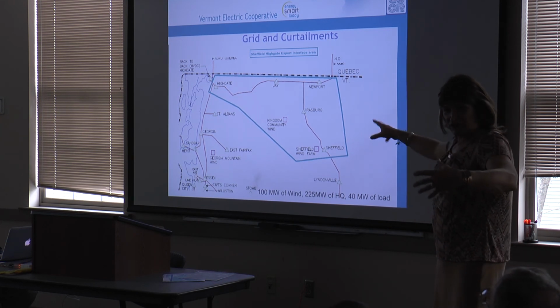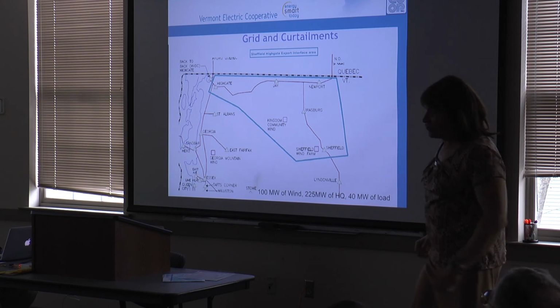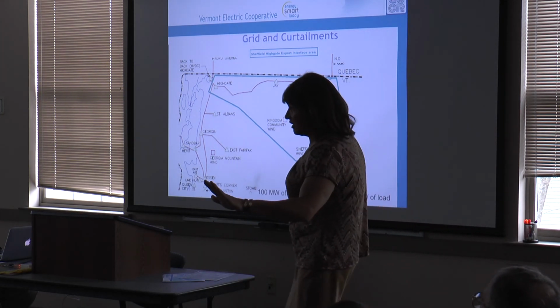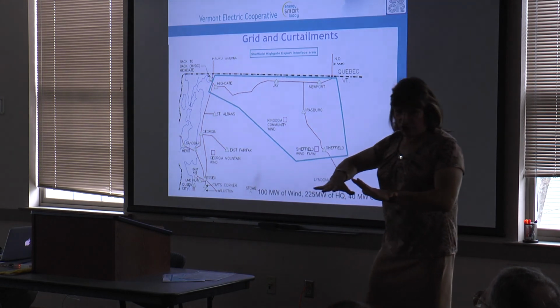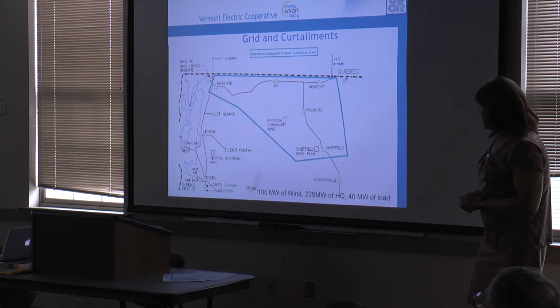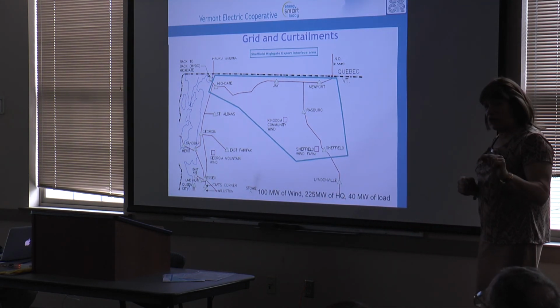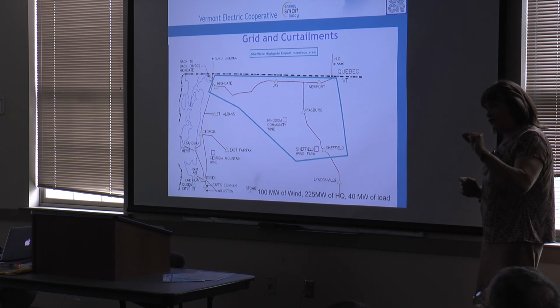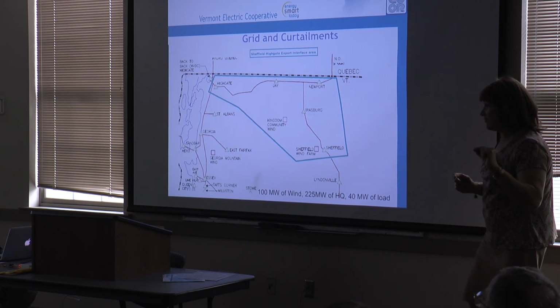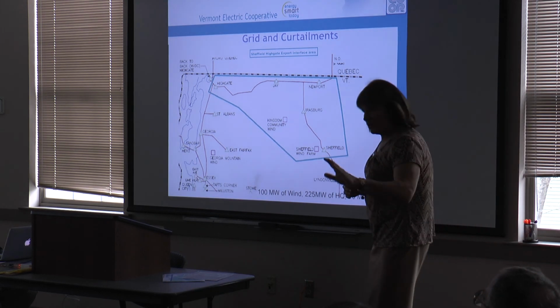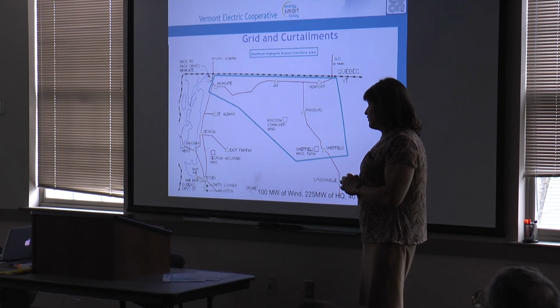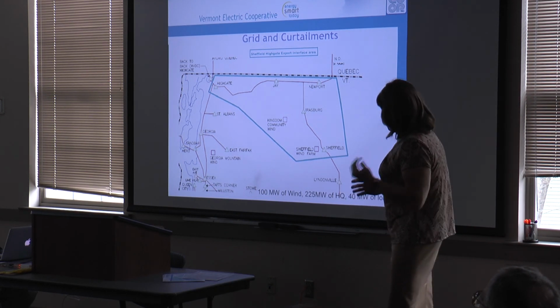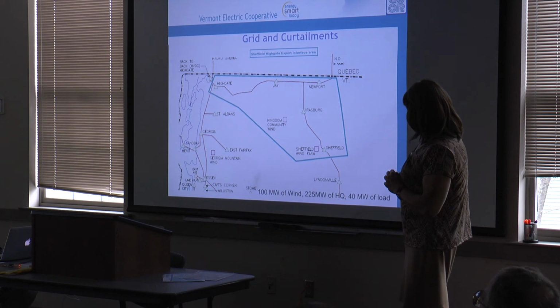That stabilizes it, but it costs about, total project cost was about 160 million, and that added 12 million to the project cost. A very significant expense. And by the way, the total round trip losses are about 5%, so we're losing about 5% of our energy. Good news is we were able to get our capacity factors up, but we had to sacrifice some efficiency.